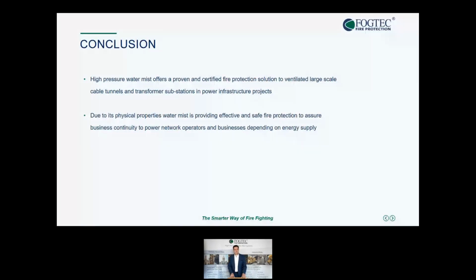You can prove the same efficiency again by additional fire tests, and these fire tests can be used for comparable projects in the future. Water mist gives a certain flexibility in power supply projects, reducing downtimes and interference on maintenance and daily business, since there is a certain limitation in the needs of a water mist system due to the smaller pipe work and smaller water amounts, which gives a certain flexibility for the systems.